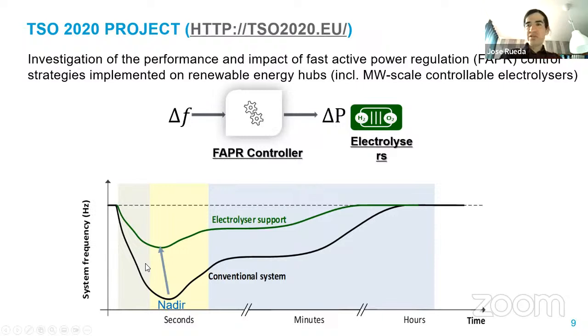We start connecting more generation units, and experience cascading loss or more loss of generation, leading to blackouts. To prevent that, I designed a control system to make these electrolyzers responsive, so they could intervene and help mitigate this abrupt frequency fall caused by less generation than demand - arresting it to an acceptable maximum deviation, and reducing the margin needed to restore it later with other control actions. This is a huge finding, because normally these kinds of devices, like other consumers, are seen as troublemakers - part of the problem.